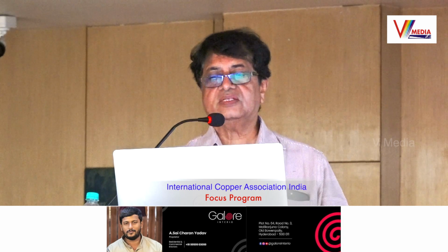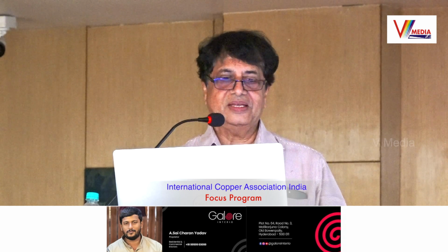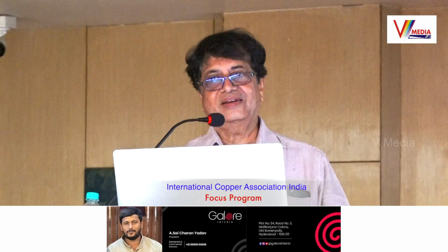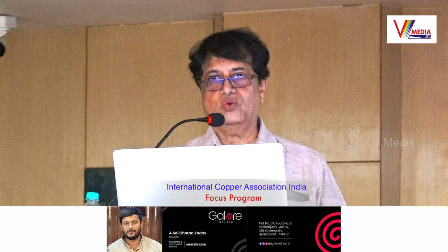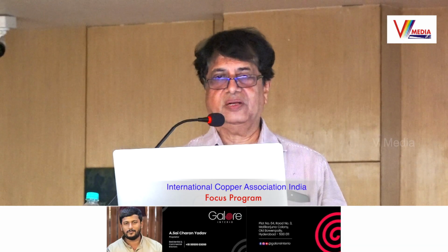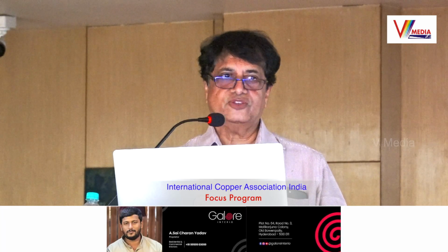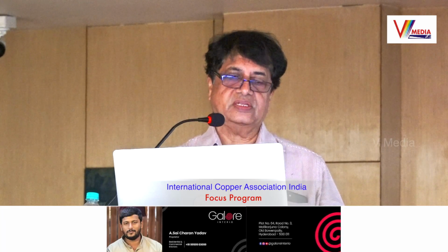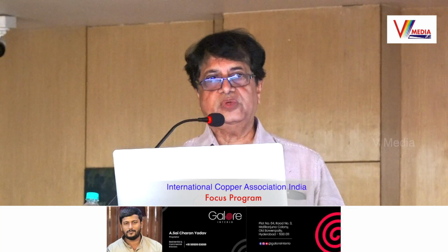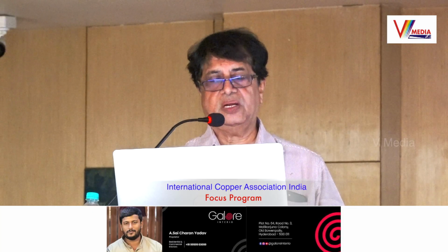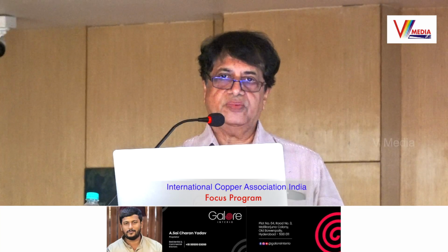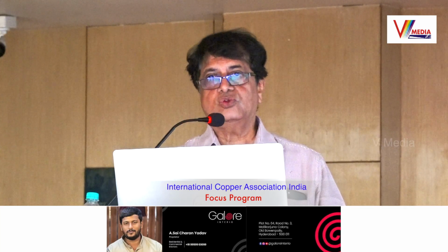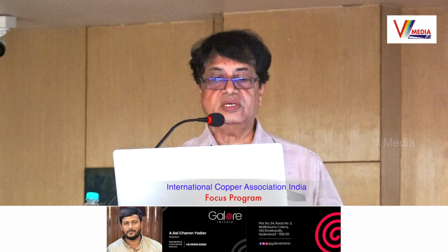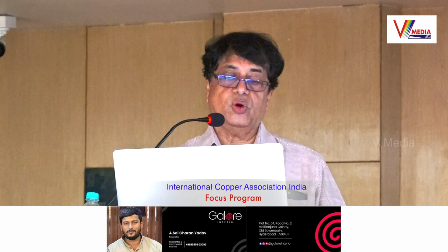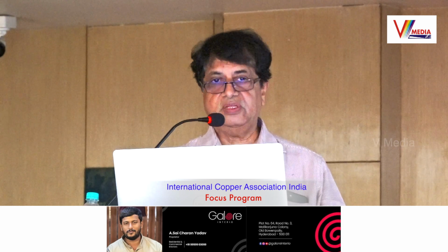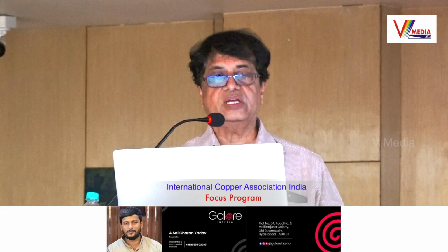Another point is aesthetics and electrical safety. So interior design is a very, very important point. And many accidents happen because the owner of a particular apartment or block, whatever it is, tries to make changes in his existing electrical installation. Why does he try to do that? Because the points given within that apartment are not as per the requirement of that particular owner or user. Those do not coordinate with the furniture layouts. Those are not placed at proper locations. The number of points given in that particular area is not the required number.